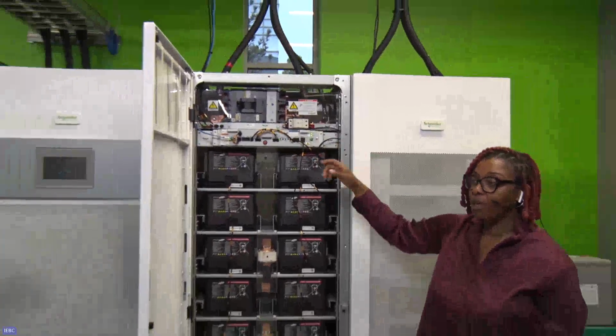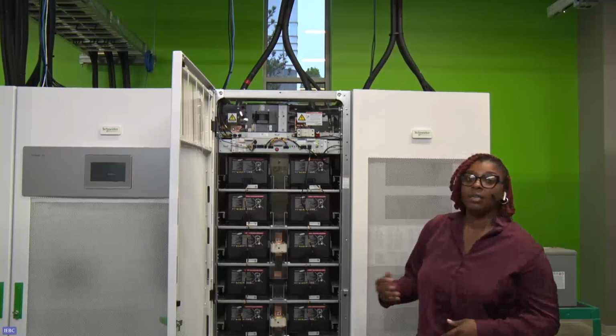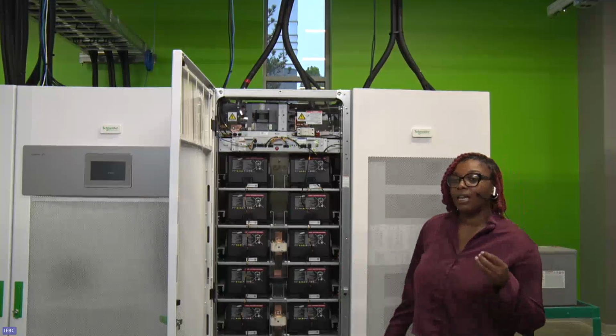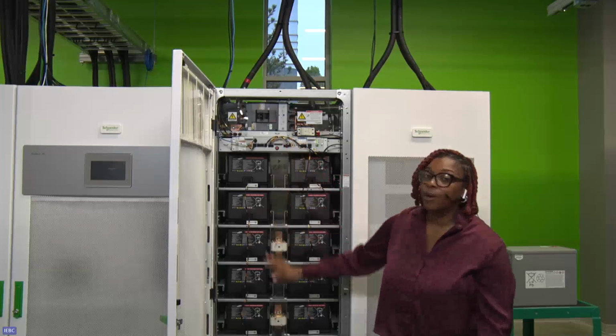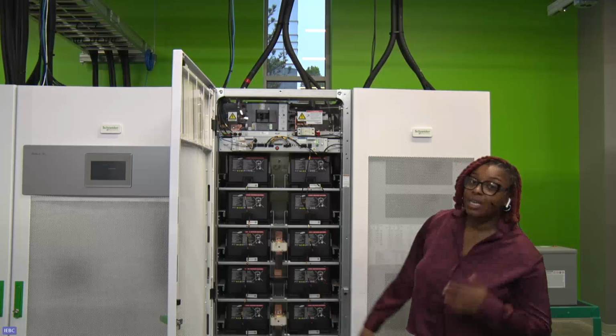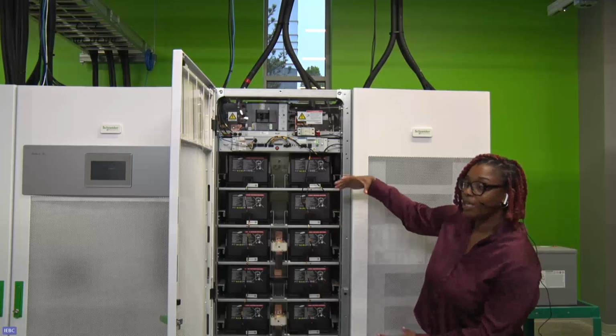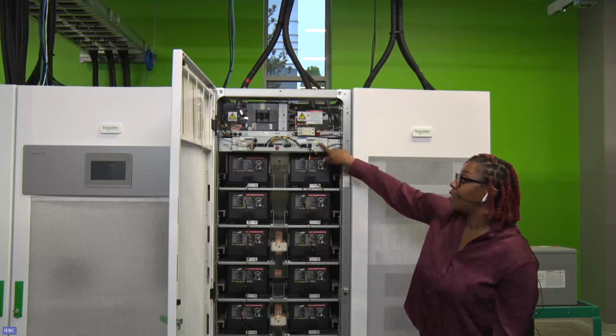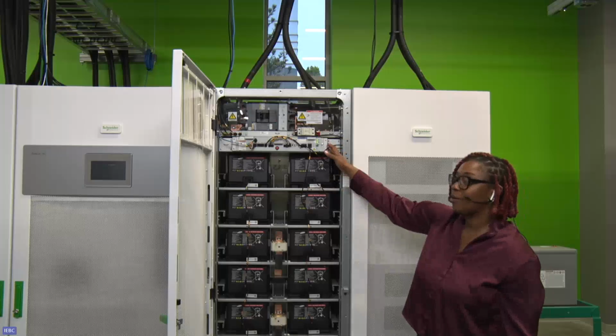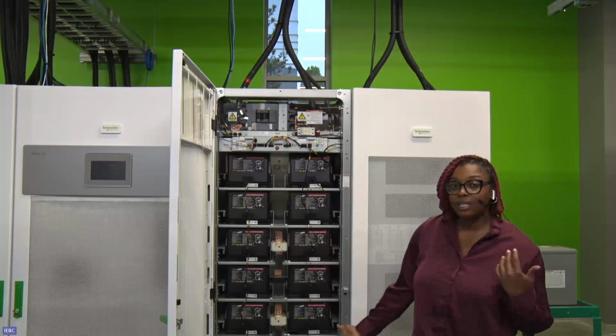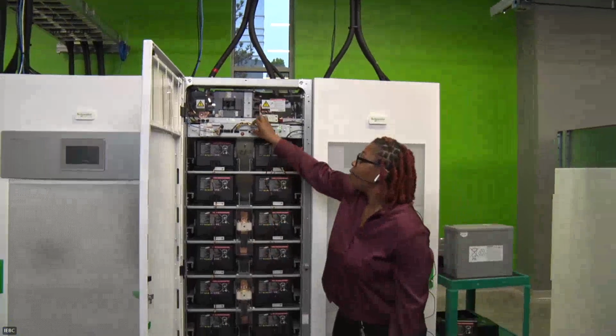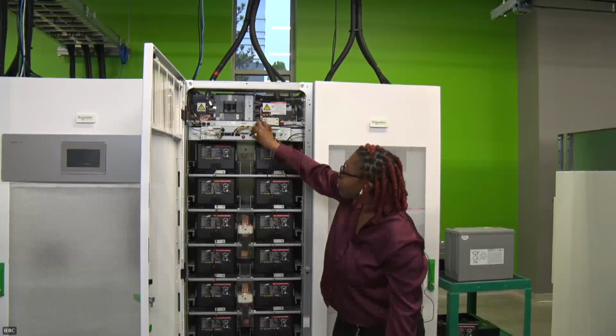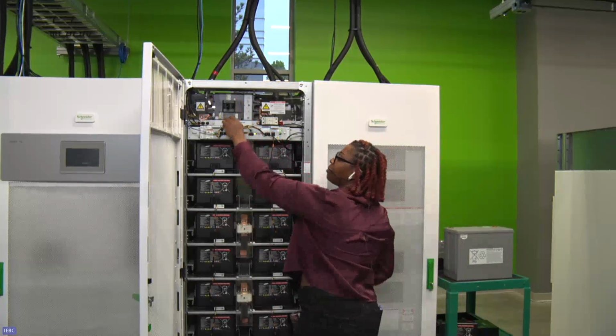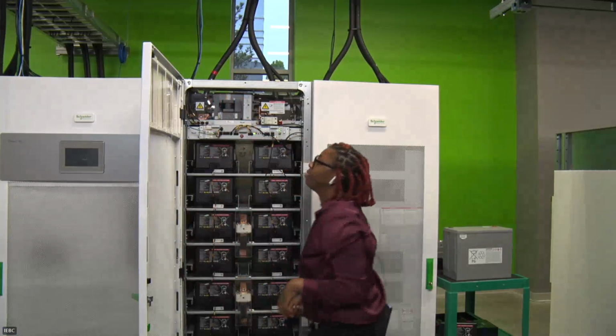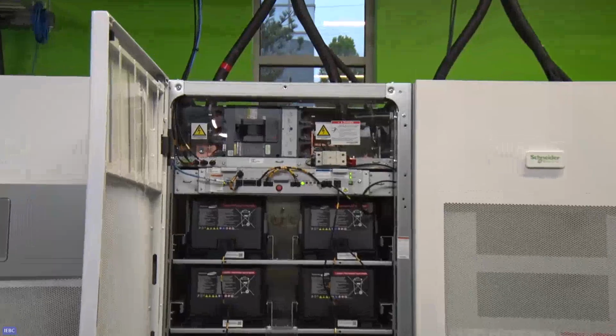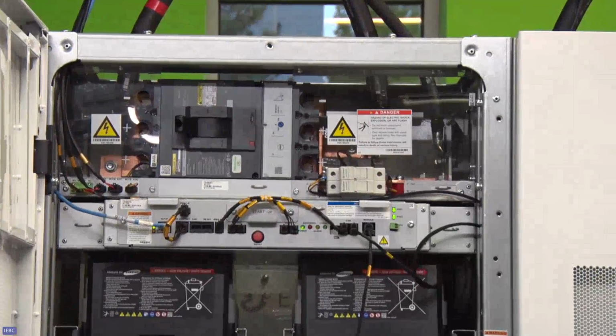We have a UVR, I mentioned that over here, under voltage relay. It's measuring a 0.3 difference in battery voltage. If that is met, this entire battery cabinet goes down. The batteries go down because it's a string. This operates as one single big battery. However, if you notice, these lights are still on. That's because our UPS is still running, and so is our battery management system. To fix this, you would go ahead and maybe replace the bad battery or fix whatever the problem was. Power gets restored. This had tripped, so I can go ahead and reset this. So we are constantly thinking about safety when it comes to lithium-ion batteries. I also want to show you the batteries here.